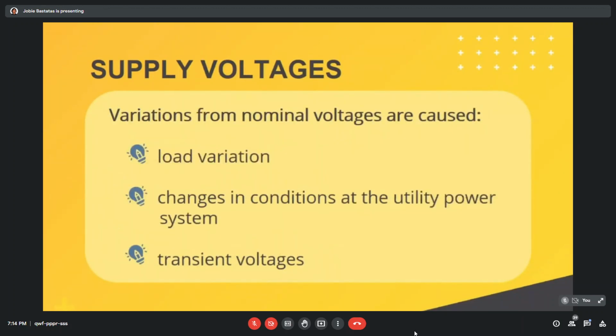Variations from nominal voltages are caused by a number of reasons, including load variation and changes in conditions at the utility power system. Additionally, transient voltages. Transient voltage is a temporary unwanted voltage in an electrical circuit that ranges from a few volts to several thousand volts. Transient voltages are caused by the sudden release of stored energy due to incidents such as lightning strikes, unfiltered electrical equipment, contact bounce, arcing, and capacitor banks or generators being switched on and off.